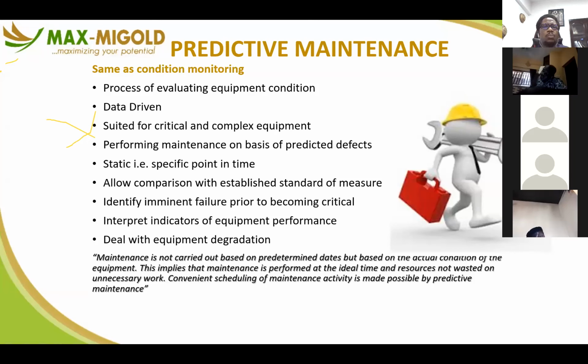Now, why is this called predictive? The way you monitor each parameter - when that data begins to tend toward going outside its control limits, you can then predict how long you have until failure, or how long you have until it goes past that upper or lower specified limit.